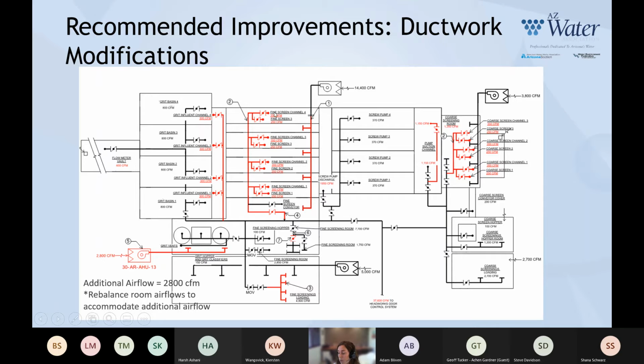We modified the channel flow from the fine screen influent channel, and then we added a duct to take flow from the fine screening equipment itself. We added a damper for the fine screen hopper area duct. And then we added channel drops into the grit influent basin, and we reduced the overall draw from the flow meter vault to accommodate that additional airflow from the grit influent channels. We also included foul air duct drops down into the fine screen truck loadout bay. With all of these changes, we added about 2,800 CFM to the system, which is how much we added for the new supply system.